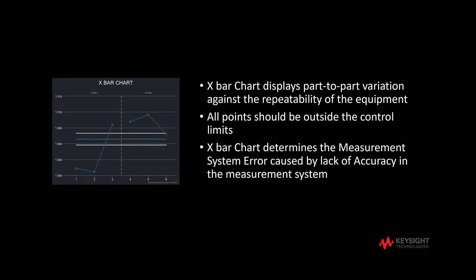The X-bar chart displays part-to-part variation against the repeatability of the equipment. Notice that all points should be outside the control limits, so that part variation can be detected in the measurement system. If the points are inside the control limits, it is difficult to differentiate whether the error is caused by the part itself or the measurement system.